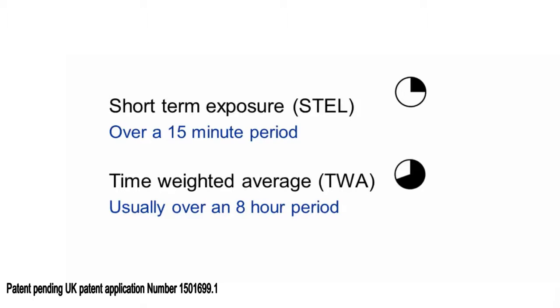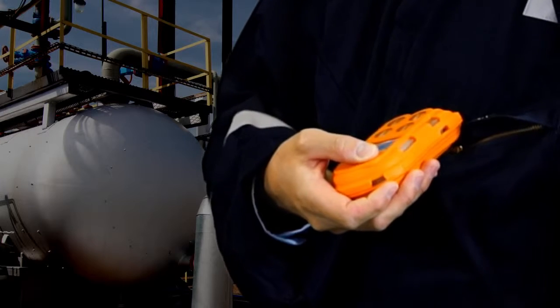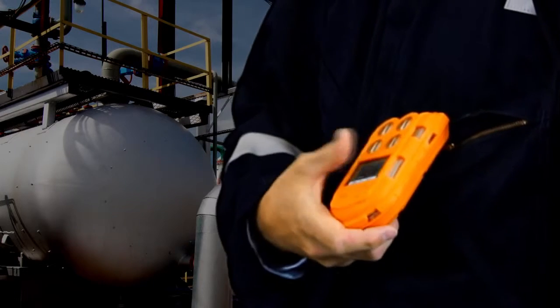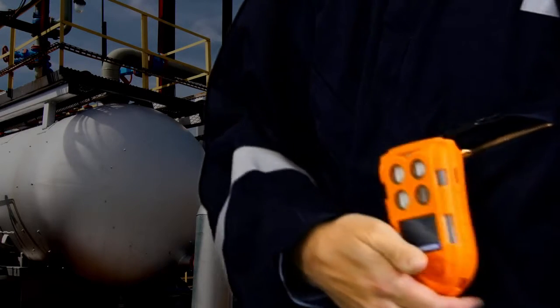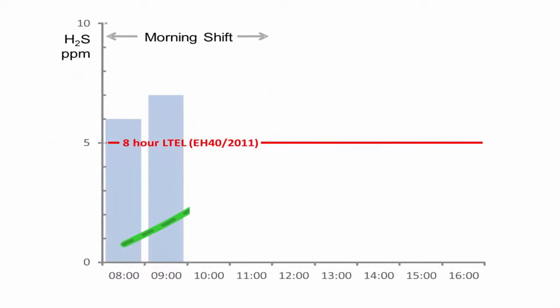When turned on, the calculation of TWA by many portable gas detector units assumes it's the beginning of a work shift. However, if the unit was switched off during a shift, for example during a break, this could risk overexposure of the worker.